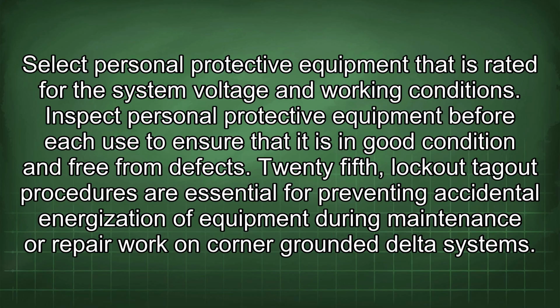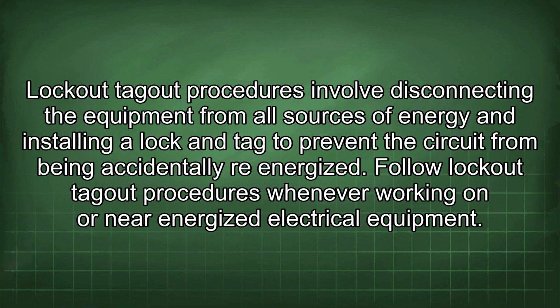25th, lockout-tagout procedures are essential for preventing accidental energization of equipment during maintenance or repair work on corner-grounded delta systems. Lockout-tagout procedures involve disconnecting the equipment from all sources of energy and installing a lock and tag to prevent the circuit from being accidentally re-energized. Follow lockout-tagout procedures whenever working on or near energized electrical equipment.